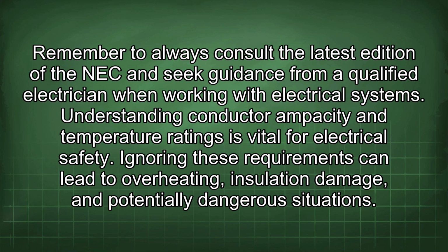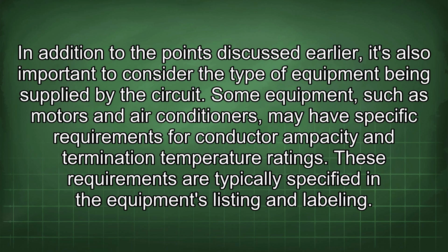Understanding conductor ampacity and temperature ratings is vital for electrical safety. Ignoring these requirements can lead to overheating, insulation damage, and potentially dangerous situations. In addition to the points discussed earlier, it's also important to consider the type of equipment being supplied by the circuit. Some equipment, such as motors and air conditioners, may have specific requirements for conductor ampacity and termination temperature ratings.